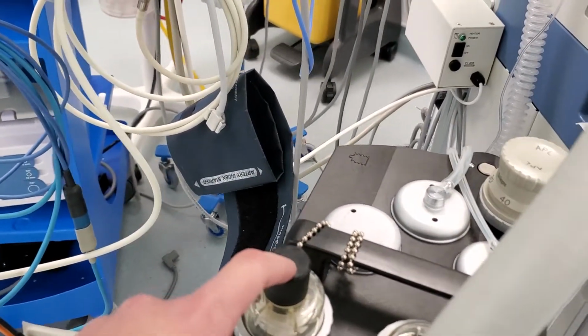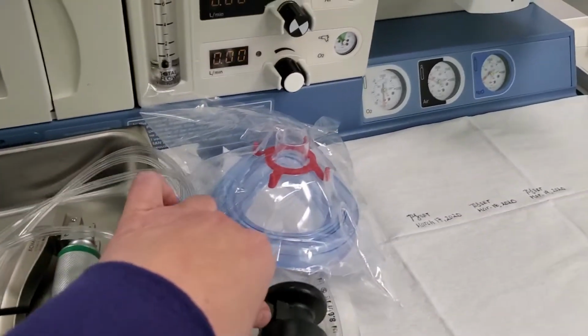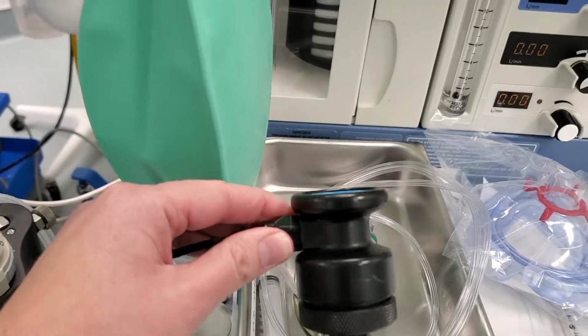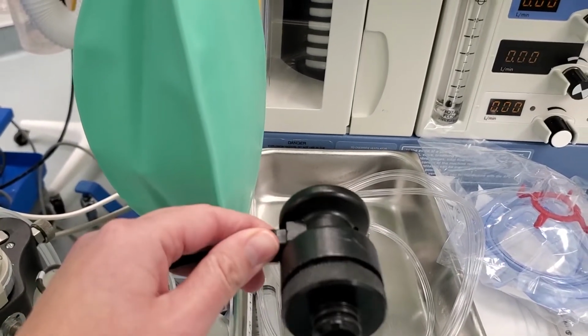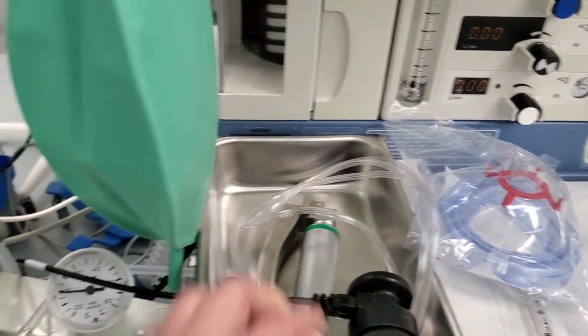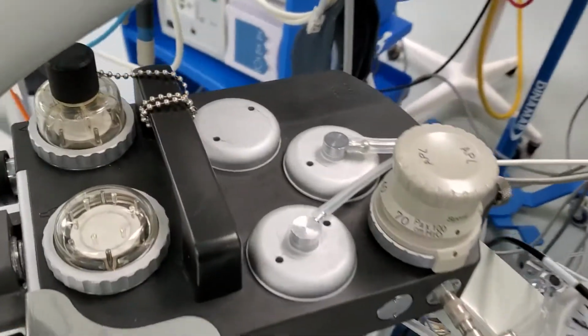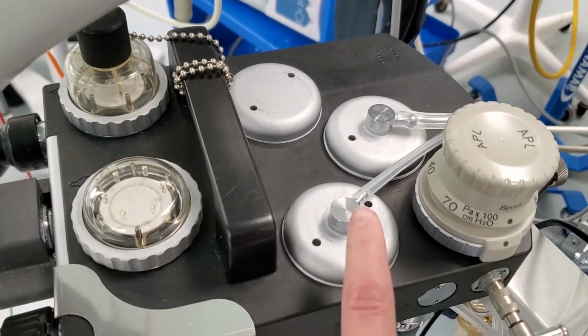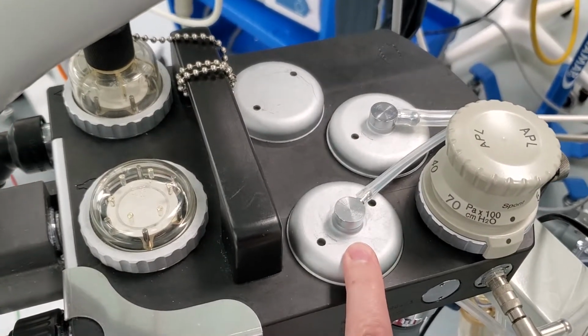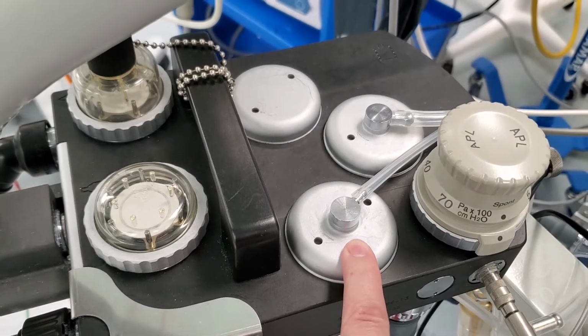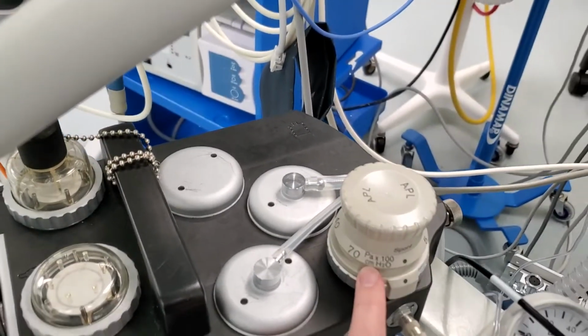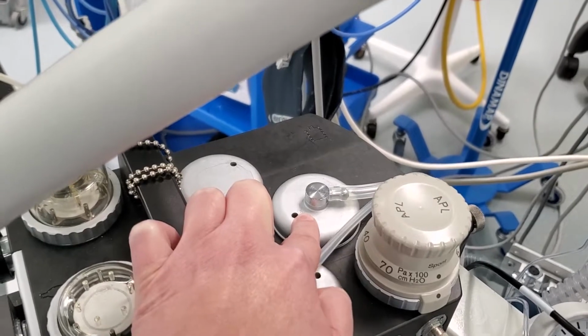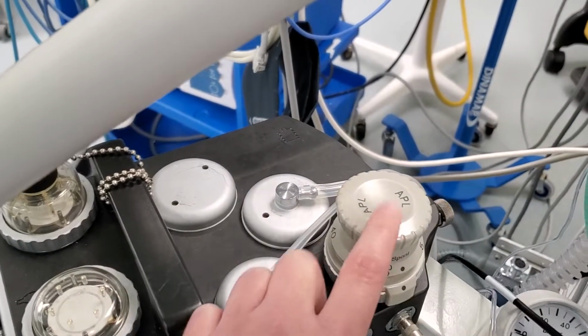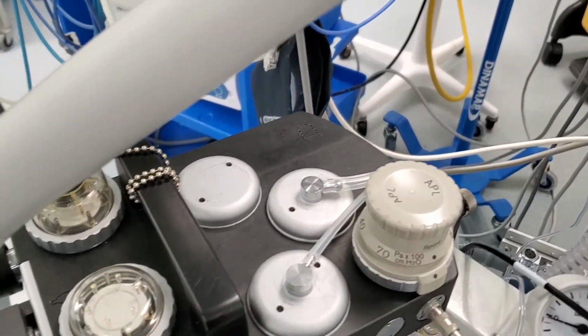We have an O2 sensor that will sit in the inspired side, and that is just taken out in between cases or at the end of the day to try to prolong the lifespan of the cell. The top of the machine here, this is your PEEP and your PMAX valve, which closes your exhalation valve to deliver a PEEP. This is your APL valve. This is your APL bypass valve. So during ventilatory modes, this APL valve is taken out of the system.